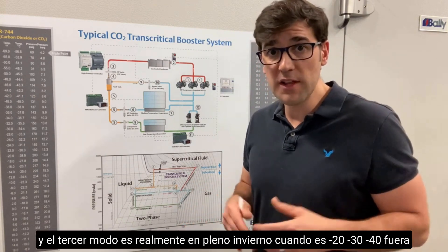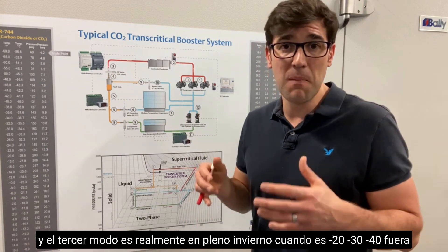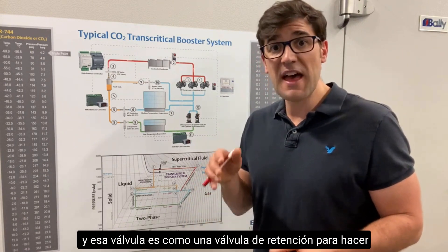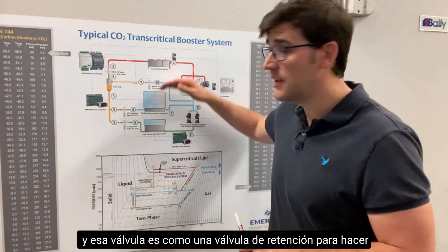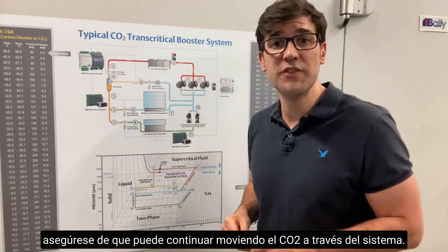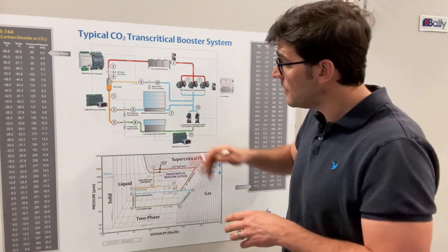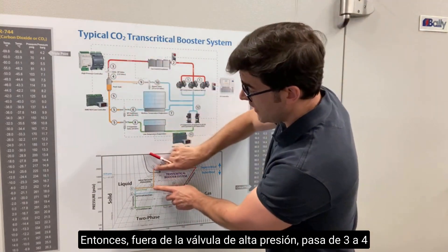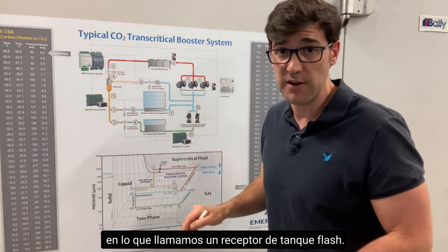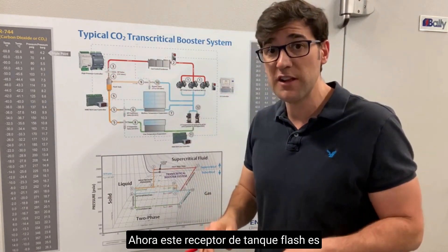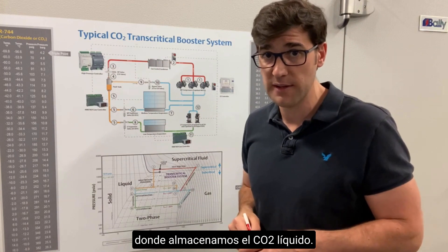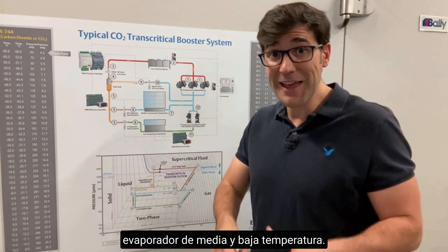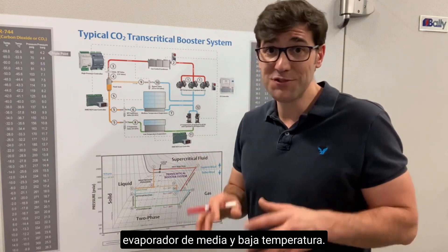The third mode occurs in the middle of winter at minus 20, minus 30, or minus 40 outside — the valve acts as a holdback valve to make sure you can continue to move CO2 through the system. Out of the high pressure valve, from three to four, you go into what we call a flash tank receiver. This is where we store the CO2 liquid, and that receiver feeds both the medium and low temp evaporators.